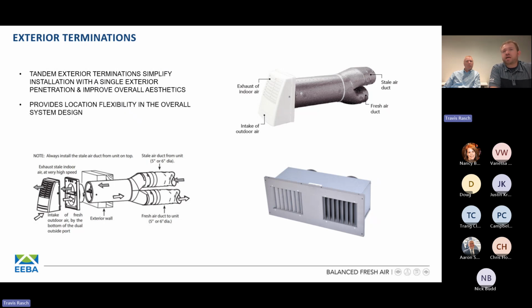So you have like a vertical stack, I'll say, so the exhaust air from the HRV or ERV is going to go out the top side of the product, and then we're going to draw that fresh air in from the bottom side, and you can see in that cross section there how we're splitting those two airflows to make sure there's a limited amount of contamination. In the case of both of these, that percentage is less than 5 or even less than 3 in the upper one. Again, we want to make sure if we're going to be pulling fresh air in from the outside, that we're not reintroducing the stale air that we just took from the inside back into it. So between the design of these types of products and the consistent velocity in which the airflows are entering and exiting, all play a factor into how we can make sure that these are limiting the contamination within it. And again, these would feed to and from the HRV or ERV in these configurations.